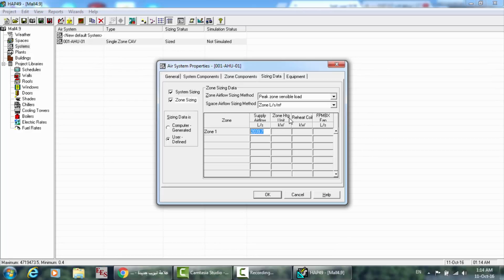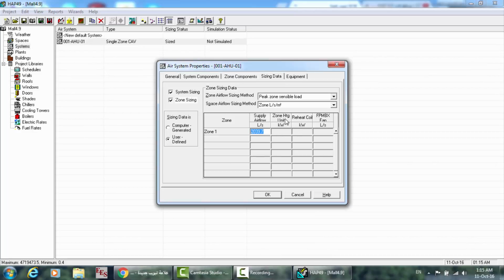And the zone heating unit, HTG, is the heating unit, in kilowatts. This is the unit of heating that you may use in this system. And the reheat coil, if you use a reheat coil, you can put the load of it in kilowatts. And the fan-powered mixing box, if you have this, you can put the airflow rate of it in liter per second. So this is the capacity of the zone heating unit and the capacity of the reheat coil and the amount of flow rate of the fan-powered mixing box.